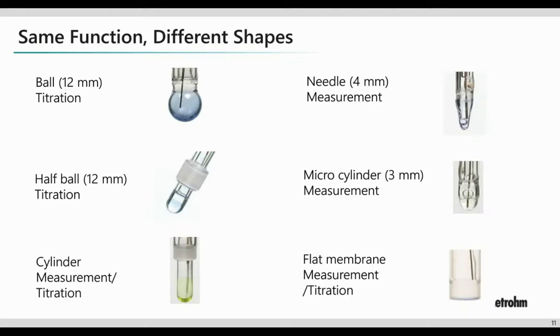You may also run into an application where you don't have a lot of sample. You still need to make these measurements. For that, there is a microcylinder. This bulb measures only 3 millimeters across. And this really small electrode only requires 20 millimeters of immersion depth. So depending on what your sample cup looks like, this can be very, very small. The last one on your screen is interesting because the entire sensor's measuring surfaces are actually on the bottom. So this means that only the bottom needs to be in contact with the sample to take a pH measurement. So here we see this design being helpful for applications where we're looking at maybe a pH measurement of a textile or a leather fabric, or even making pH measurements on skin.